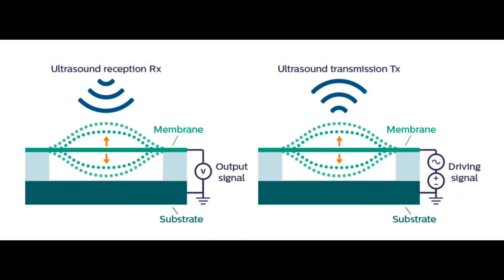Can you tell a bit more about how this ultrasound is produced? The traditional way is by using piezo material, which is vibrating ceramic material — a sort of rock that vibrates when you put a voltage over it. In this case, we eliminated the piezo material and make use of a vibrating membrane, a drum. We put a voltage across it, it vibrates, generates a pressure wave, and senses back the pressure wave that returns. It sounds very simple, but obviously developing and producing this is a whole different ballgame with a lot of technology going in.